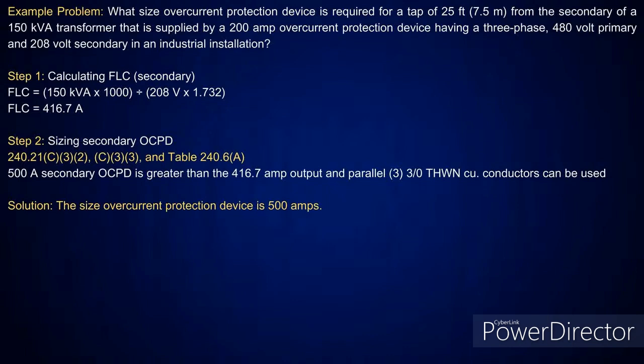Then you go over and you look at table 240.6. What's the next size above that 416.7 amps? It's 450 amps. So you've got a 500 amp overcurrent device. Now, why would I go up? Well, if you look at the standard sizes for the overcurrent devices that are rated 800 amps or less. Okay, and that's pretty basic how you go about calculating this.